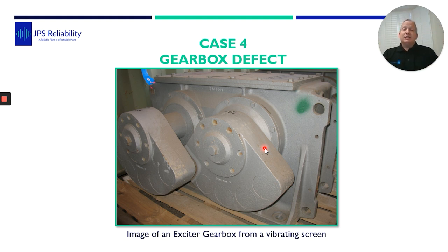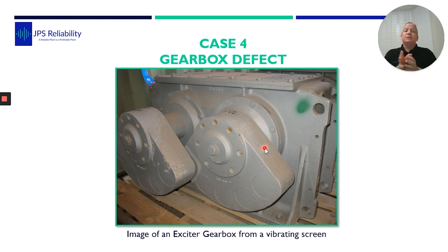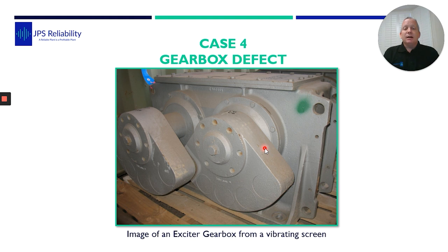At this particular site they were having problems with gearboxes failing. Their current method of detecting failure was the operator walk-around — they would use a temperature gun and when it was hot they knew it was going to fail within the shift. The issue here was that the detection PF interval was too short; they would then panic and try to get a replacement. We offered to do a vibration analysis survey to see if we could find a defect earlier.